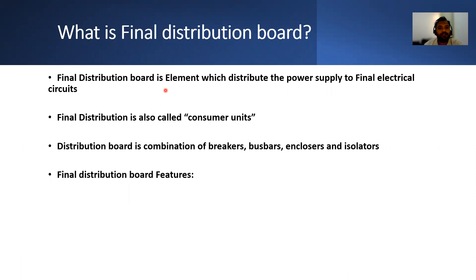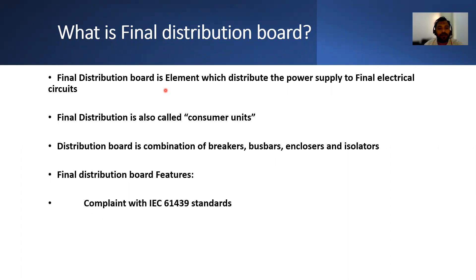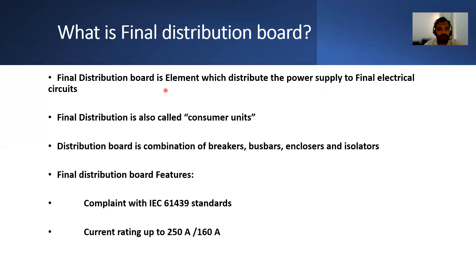Final distribution boards are compliant with IEC 61439 standards, with a current rating up to 250 amperes and a short circuit withstand capacity of 17kA for 200 milliseconds.